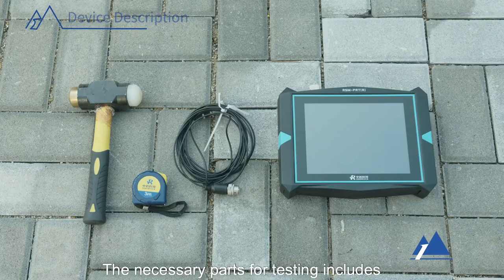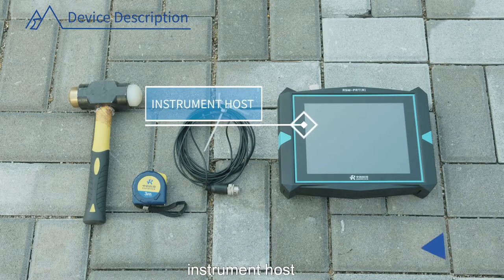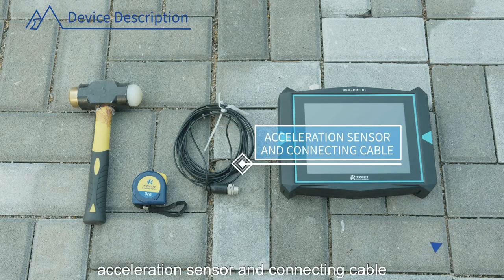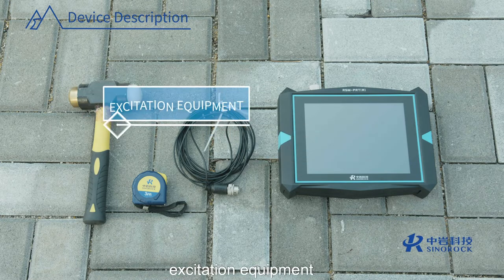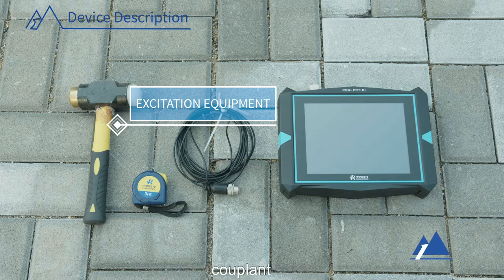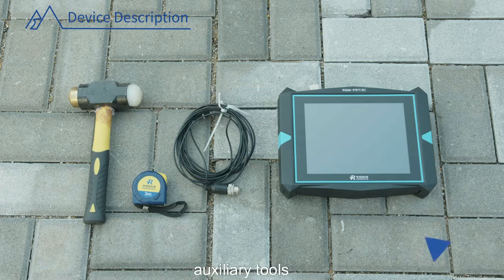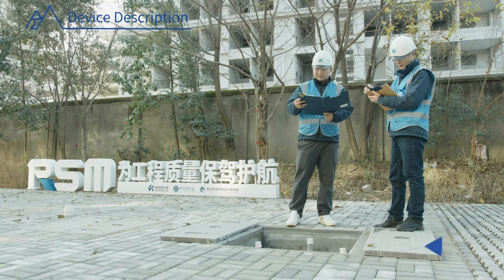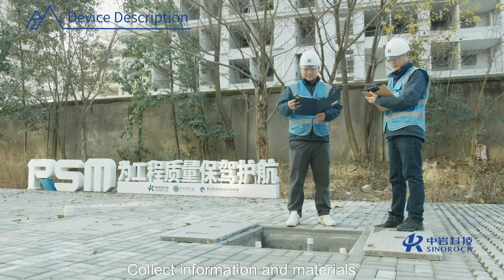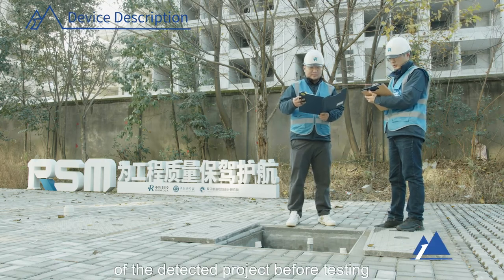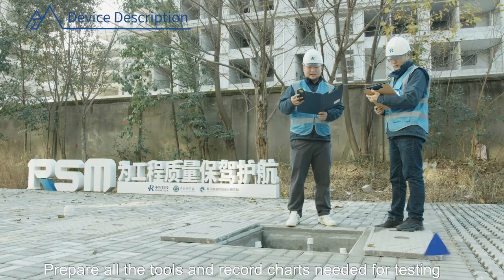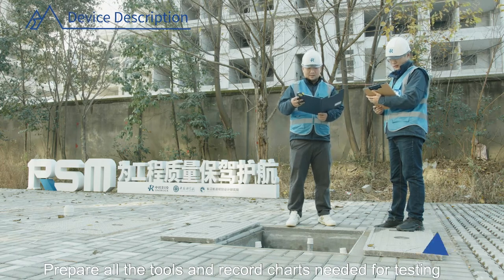The necessary parts for testing include the instrument host, acceleration sensor and connecting cable, excitation equipment, couplant, power charger, auxiliary tools, etc. Collect information and materials of the detected project before testing. Prepare all the tools and record charts needed for testing.